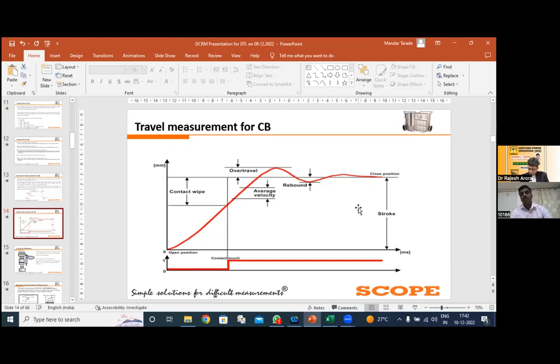Also here, 10 milliseconds prior to your first touch is the first point, and then the first touch point. The slope between these 2 points will give you the value of the average velocity at the time of closure. In case of tripping, it is exactly the reverse, because whenever we perform the tripping operation, the first point is the first tripping point and the second is 10 milliseconds after tripping. So the slope between these 2 points will give you the idea about the average velocity at the time of tripping. So this is about the default velocity.